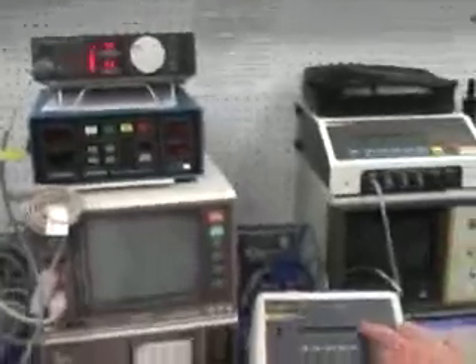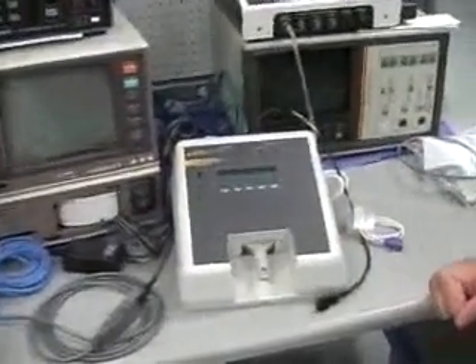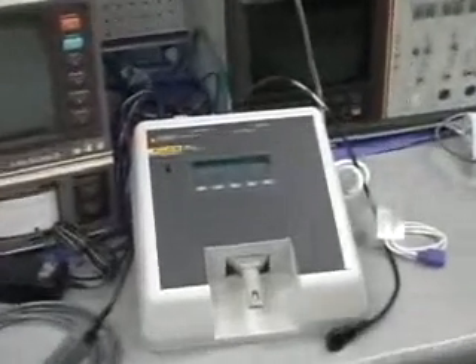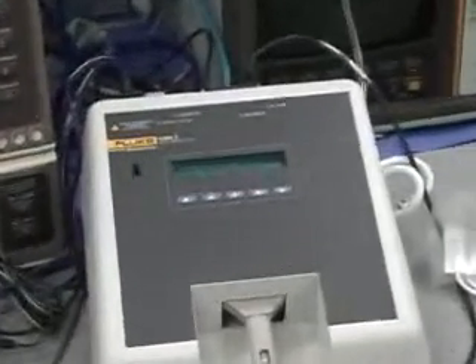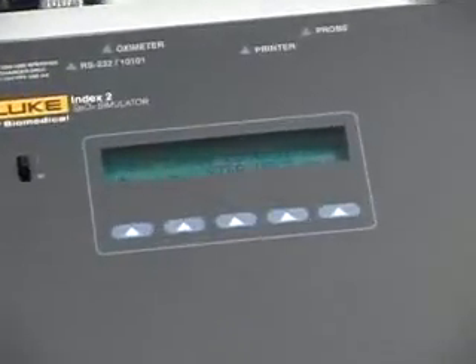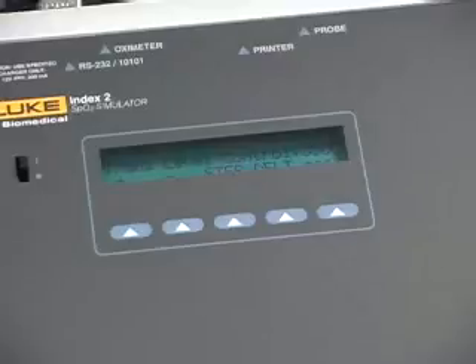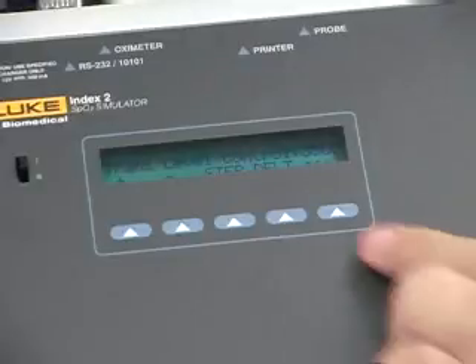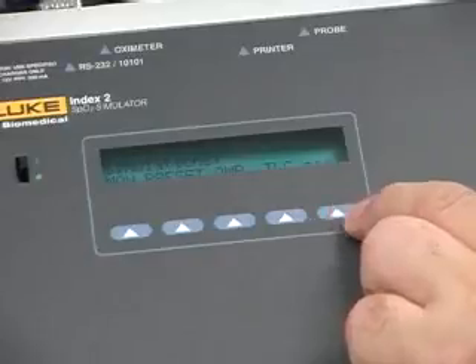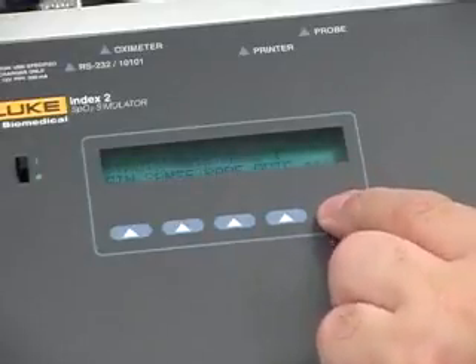Right now the TLC on this one is set to about 3,500. That's out of a maximum of 4,096. That's the maximum range, 0 to 4,096, 12 bits. Yep. We went right past the 512 and it kept on going. With this, you're able to set those levels. The default for the Nonin Medical got set too low.